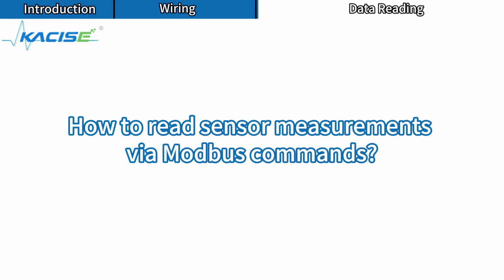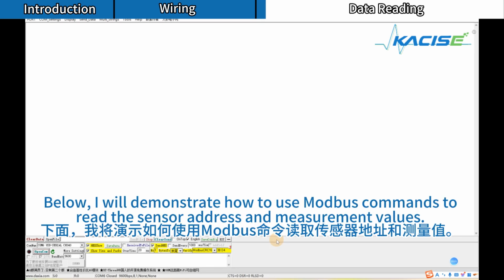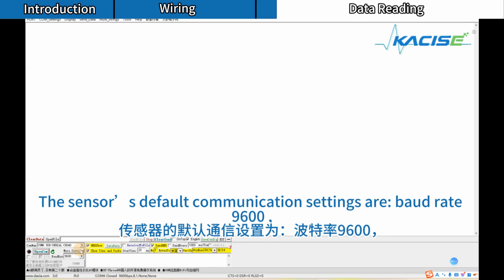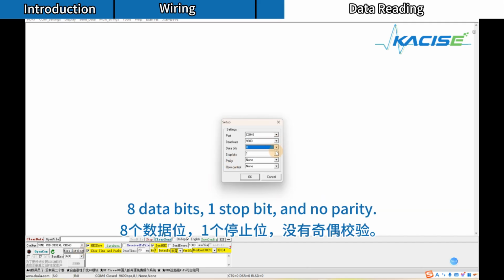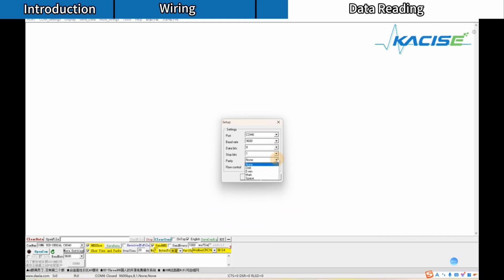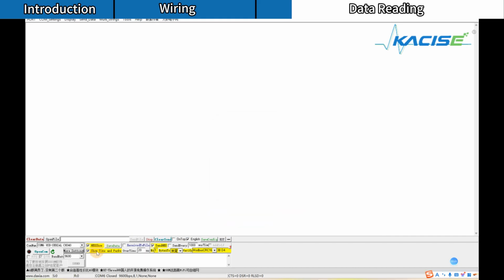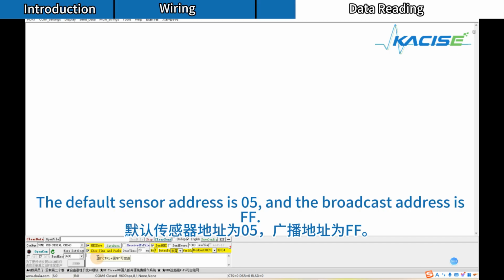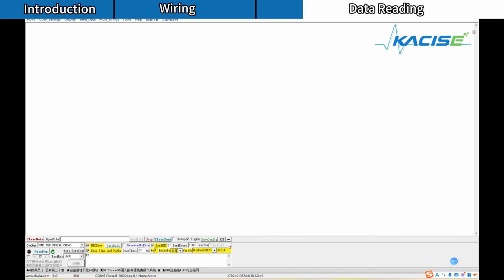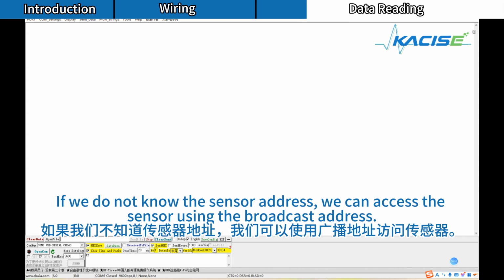How to read sensor measurements via Modbus commands. Below, I will demonstrate how to use Modbus commands to read the sensor address and measurement values. The sensor's default communication settings are baud rate 9600, 8 data bits, 1 stop bit, and no parity. The default sensor address is 05, and the broadcast address is FF. If we do not know the sensor address, we can access the sensor using the broadcast address.